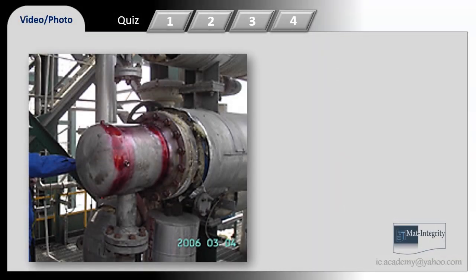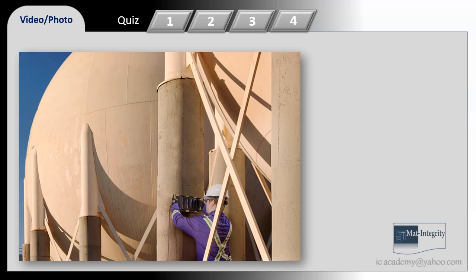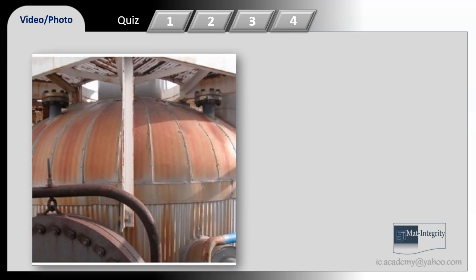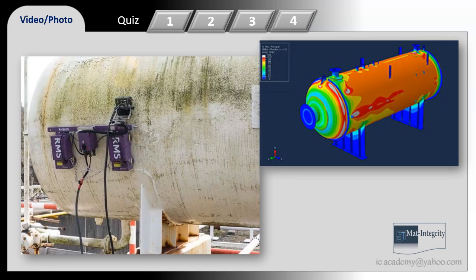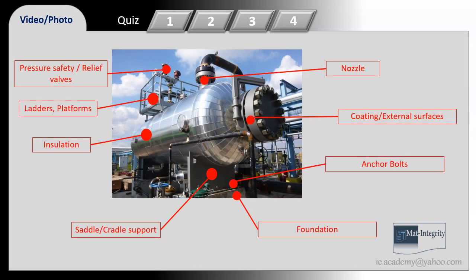Pressure vessels shall be periodically inspected to assist in assuring safe operation until the next scheduled inspection. These inspections shall assess the condition of the pressure equipment for integrity and its fitness for service until the next scheduled inspection, at the pre-estimated design conditions and normal operational parameters. Inspection may be both internal or external, and may include supplementary non-destructive techniques, or pressure tests. The external inspection gathers information about the condition of external surfaces of pressure equipment, and as a minimum, includes inspection of the external components, as shown in this figure.